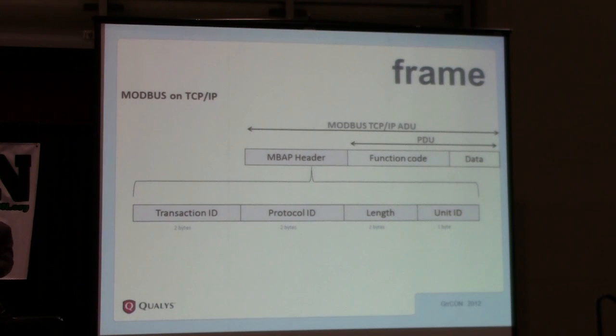this question, hey, this is question number 1, what is the pressure on unit number 10? And then you get a response back saying, oh, this is the answer to your question number 1, and this is the pressure on unit number 10. So there can be many units, and that's basically what the unit ID is. You can say this is question number 2, now tell me what's the temperature on unit number 100, and so on and so forth. So everyone good here? All right.